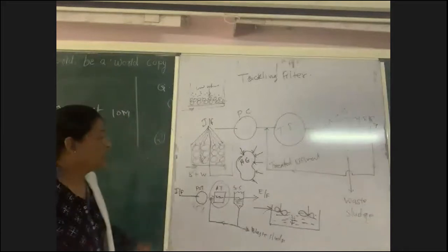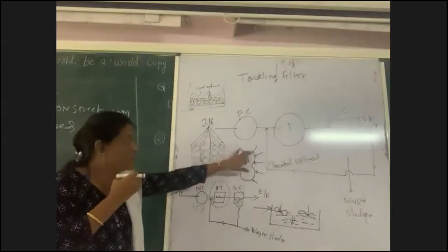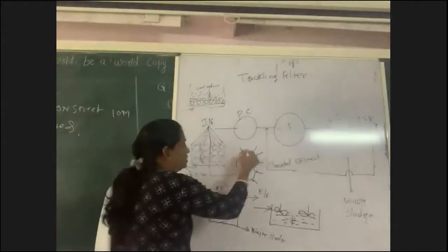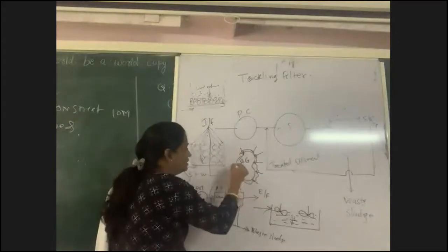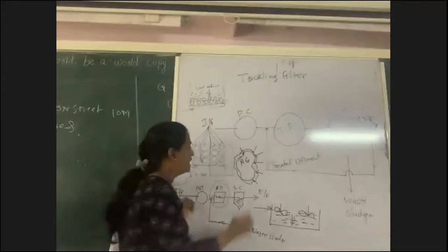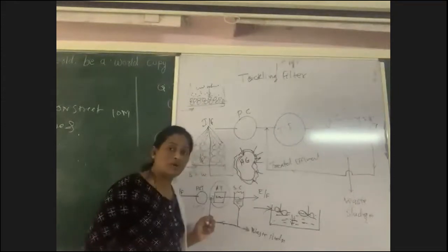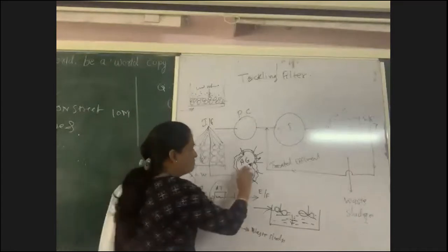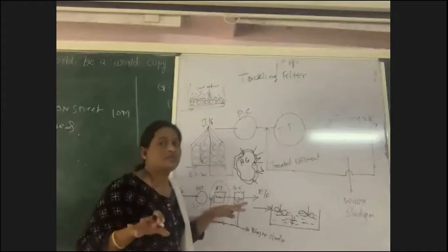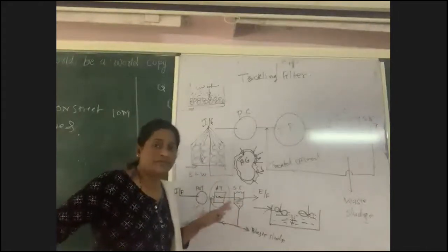Now, when it is an attached growth process, it will remain in attached form. So it will keep forming a layer around the surface of that particular object, and as time passes, the layer thickness will go on increasing, and after some time it will start falling down, detaching, and that detachment is known as sloughing.